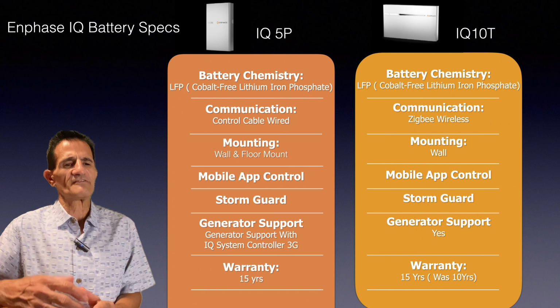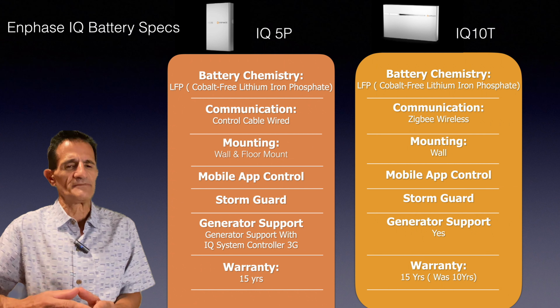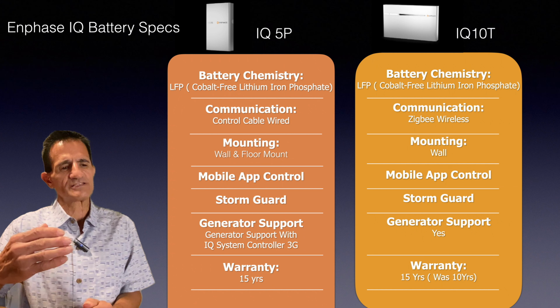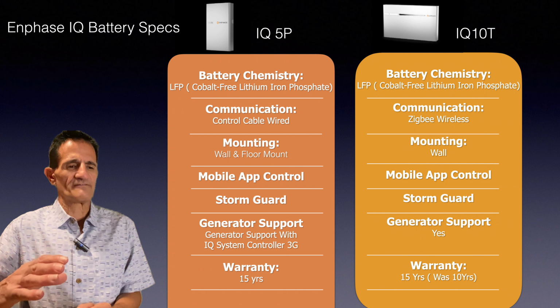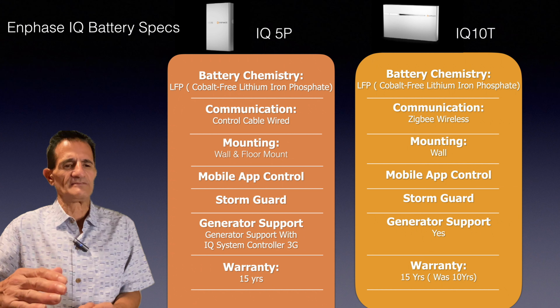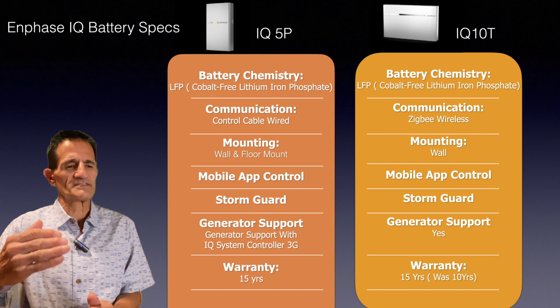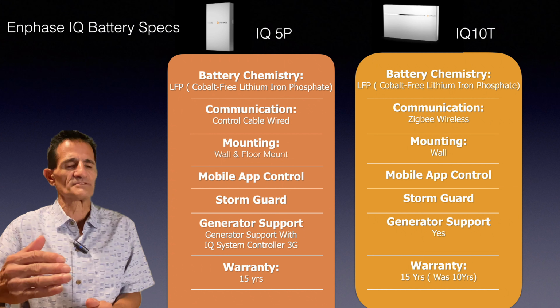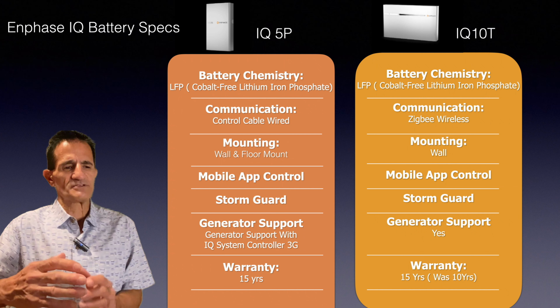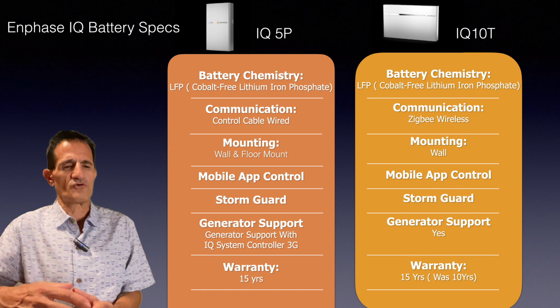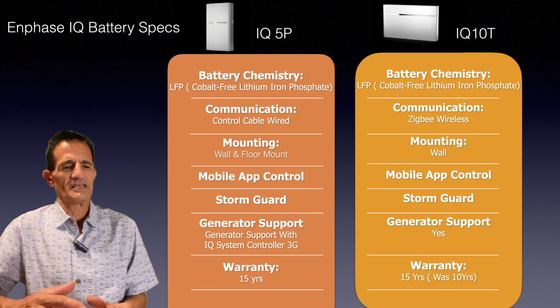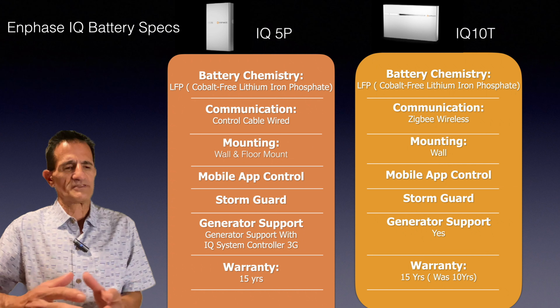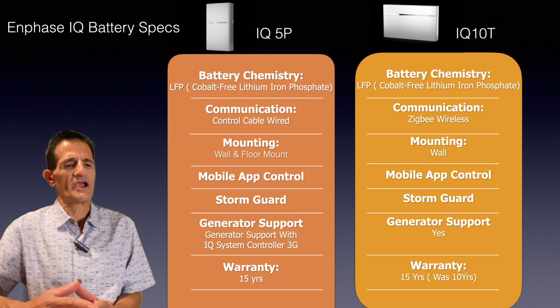The communication for the 5P is wired versus the 10T, which is wireless. You'd think wireless would be an advantage, but in-field experience tells me wireless sometimes actually causes problems—you're in a bad area with interference, or different components can't go together on the same wall, so you end up with communication problems. So wired communication is actually highly preferred.